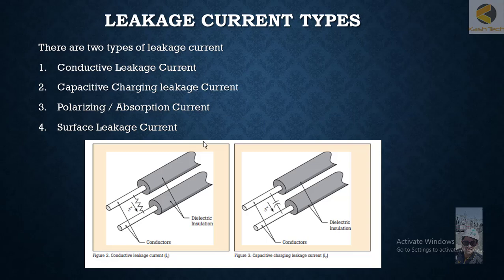The third type is the polarizing absorption current. Whenever DC voltage is applied, the molecules align themselves in the direction of the positive and negative poles respectively, causing a flow of charge in the conductor. This flow of charge is a kind of displacement current and is called the polarizing current, which is also added to the leakage current. These second and third types will be discussed separately in detail.